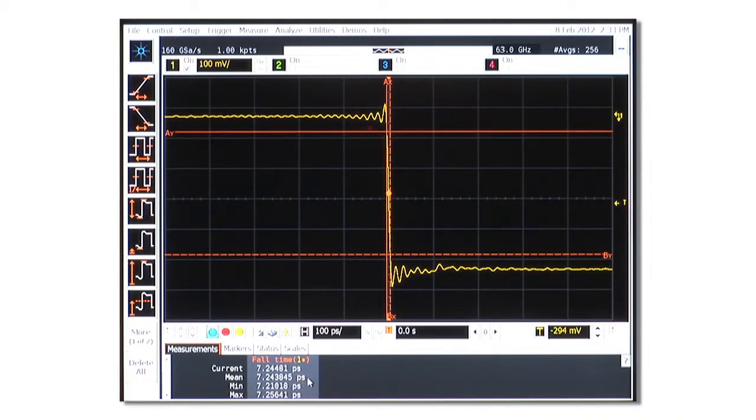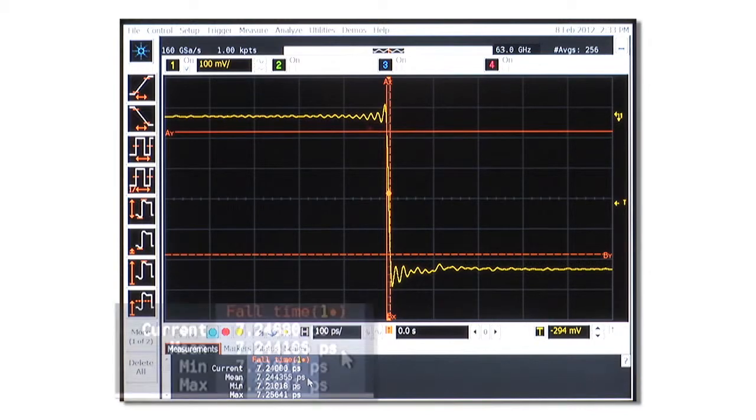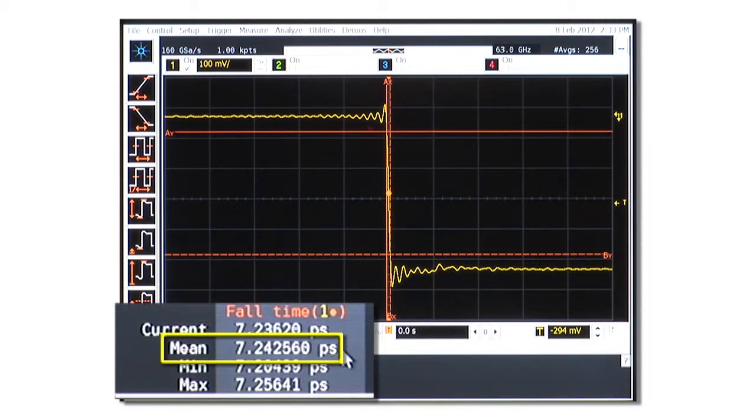What kind of rise time can you measure with a full 63 GHz of bandwidth? We've set up a rise time measurement using the calibration output of the scope and Agilent's new N2807A ultra-fast pulse generator, which accelerates the cal out edge to 7 picosecond rise times.